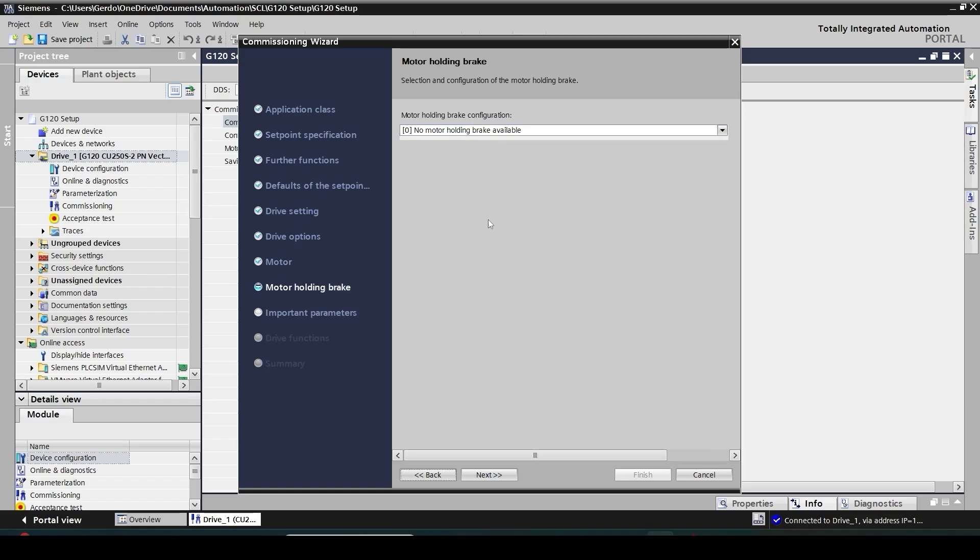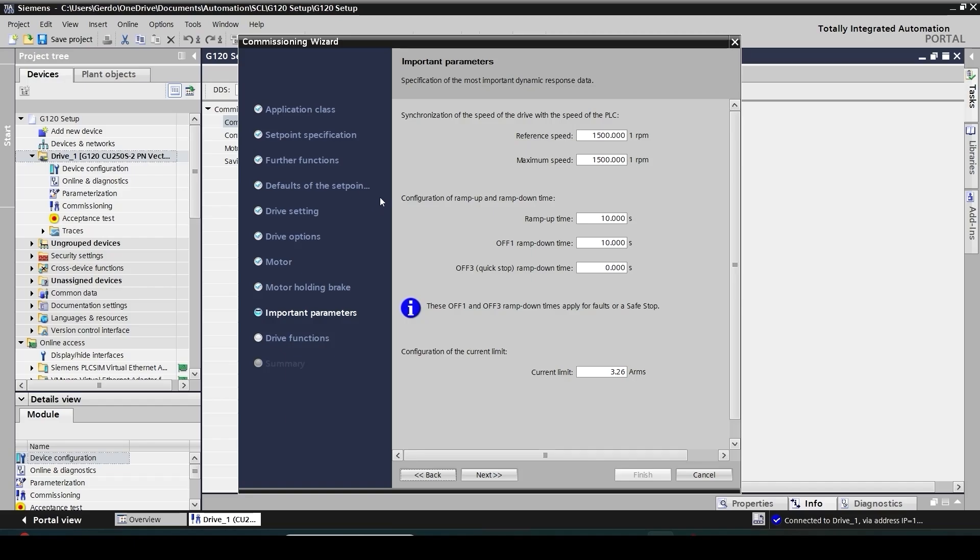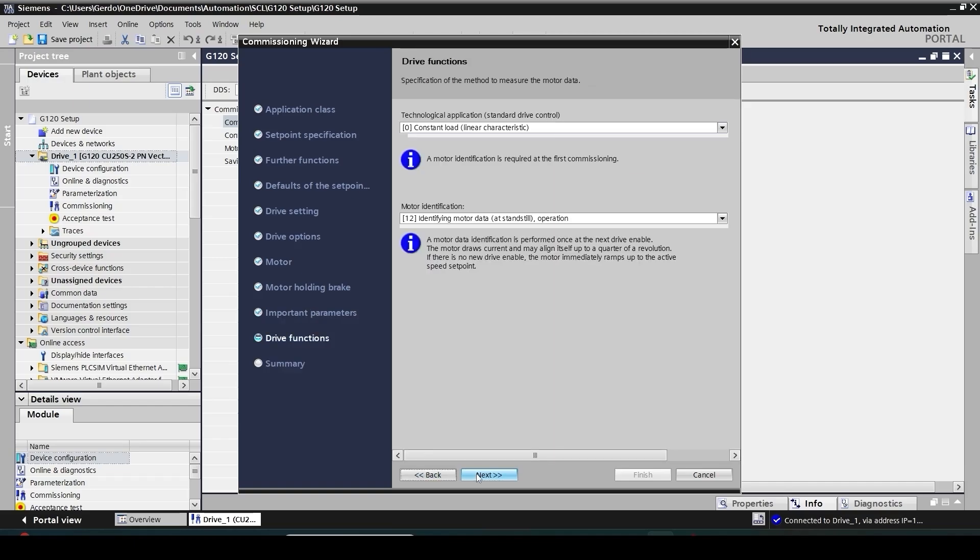Do I have any brake? No. Next. Here you need to specify some parameters like speed reference for calculating the speed setpoint. Since I have selected the motor, this information has been automatically loaded but you can also make sure that they are in range. You can verify this information with your motor nameplate. In my case, my motor nameplate shows nominal RPM of 1440, which is in line with 1500. Then click next.